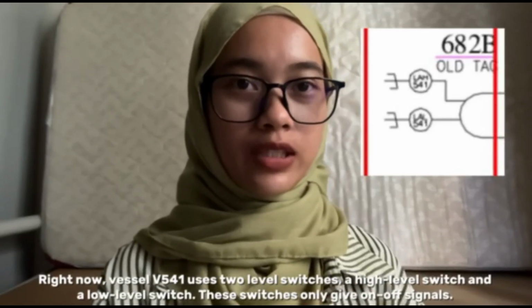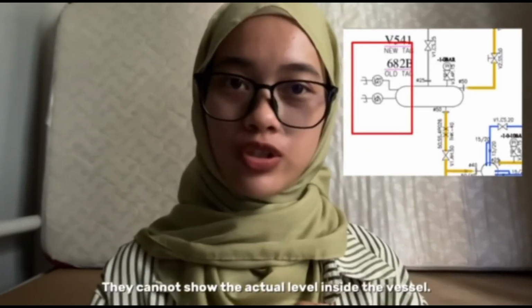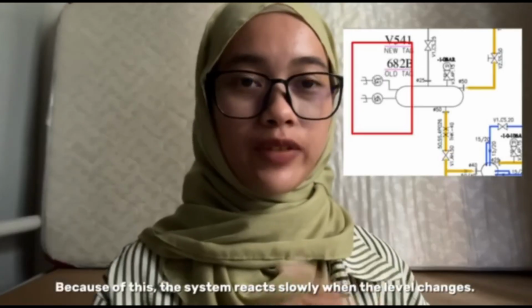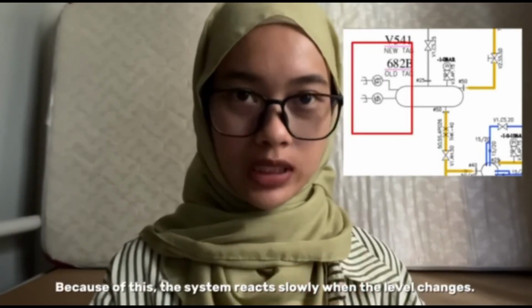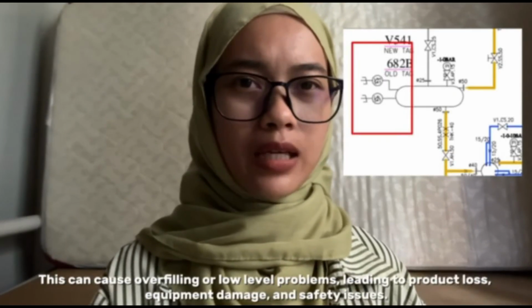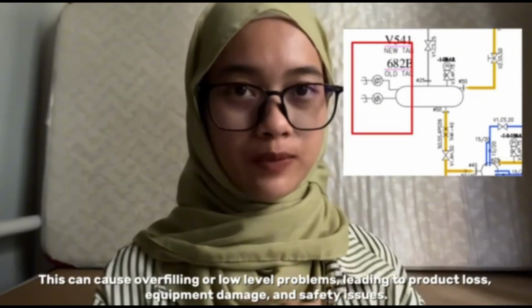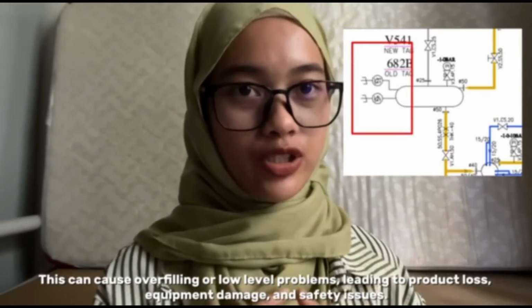These switches only give on or off signals. They cannot show the actual level inside the vessel. Because of this, the system reacts slowly when the level changes. This can cause overfilling or low level problems, leading to product loss, equipment damage, and safety issues.